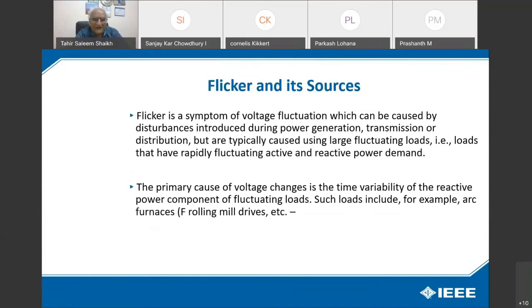Flicker is a symptom of voltage fluctuation, which can be caused by disturbances introduced during power generation, transmission, or distribution, but is typically caused by large fluctuating loads, either loads that have rapidly fluctuating active or reactive power demand. The primary cause of the voltage changes is the time variability of the reactive power components of the fluctuating loads. Such loads include, for example, arc furnaces, rolling mill drives, etc.